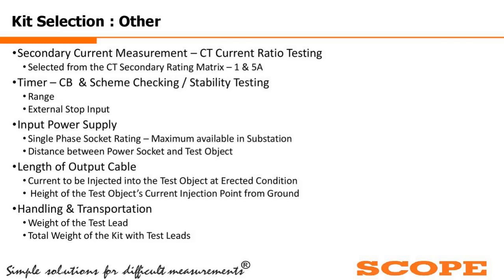Regarding the length of the output cable: when testing a current transformer, the height of the CT from ground level is roughly 5 to 7 meters, so the output cable length must be selected accordingly. We calculate the current to be injected at erected condition and the height of the test object to set the specifications. For handling and transportation, the weight of the test kit should be as low as possible — both the individual unit and total weight including test leads. These are all the parameters we need to consider for selection of a primary current injection test set.